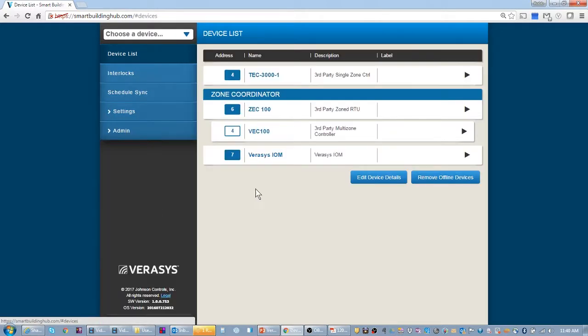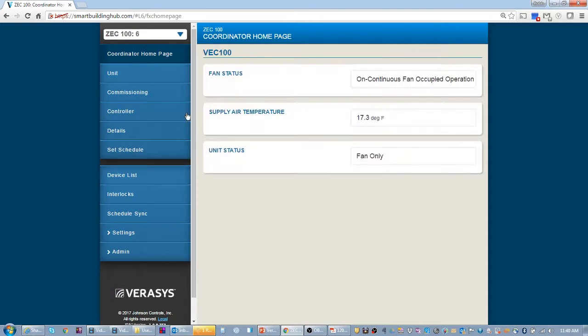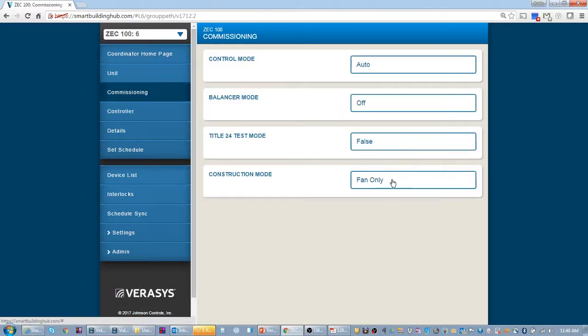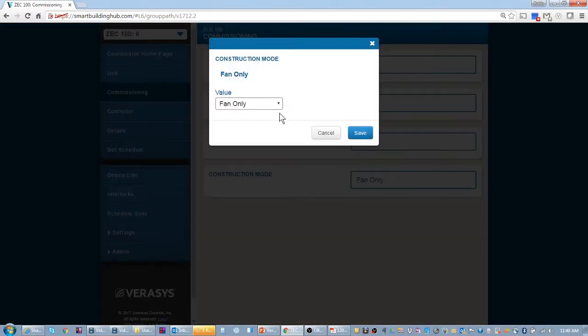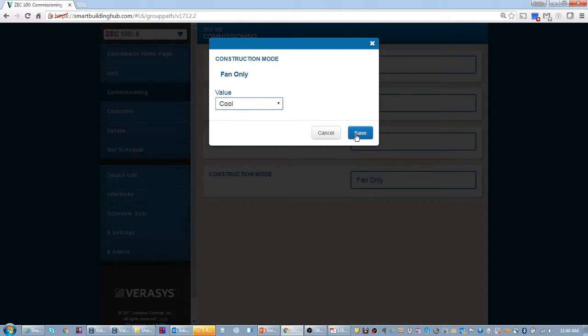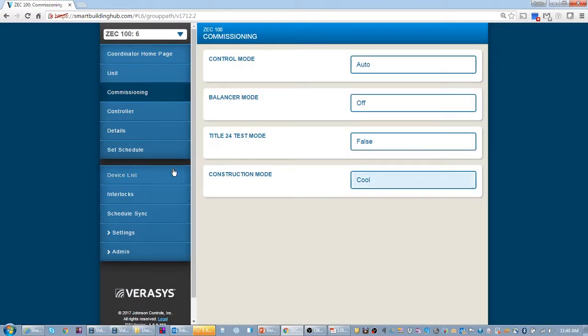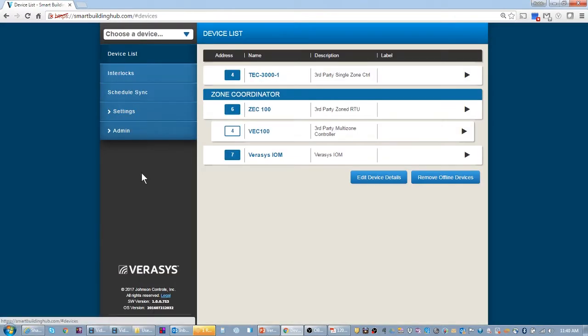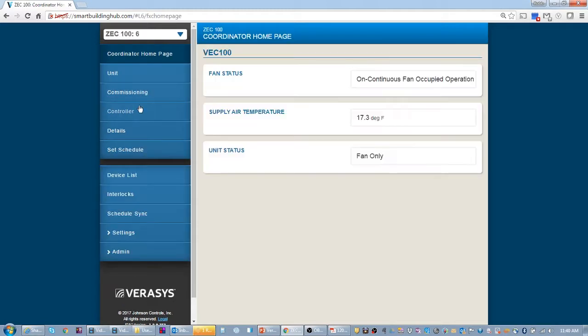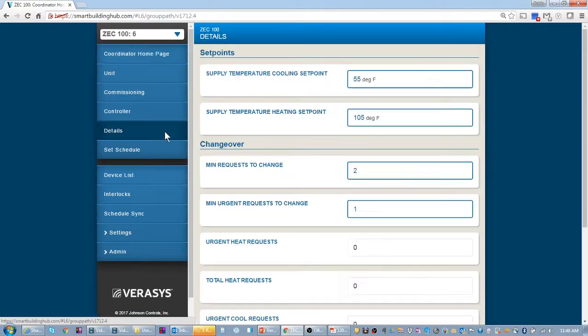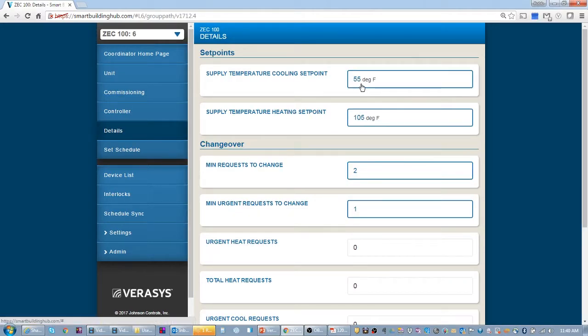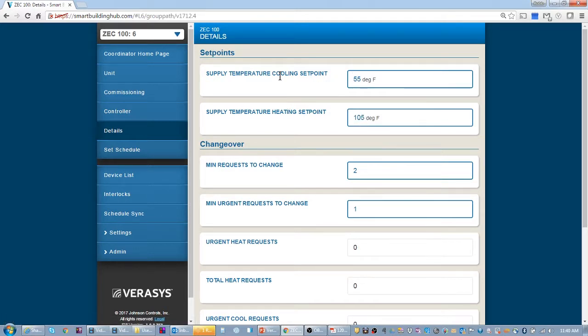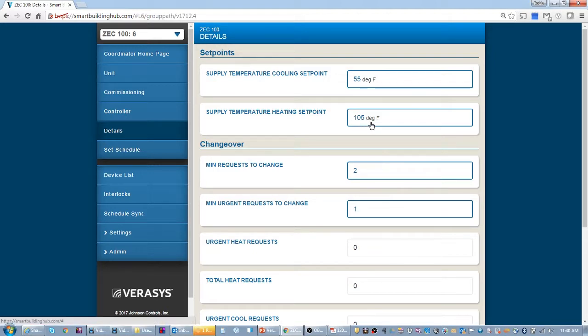Again, I could go back and put it to cooling. So come back to commission. Let's put it to cooling. Now what that'll do should have jumped out. That means that the unit will now try to control to 55 degrees. So if I want to adjust that a little bit, I could trim that some. Conversely, if I would have set it to heating, I could control what is the discharge coming out of the unit.